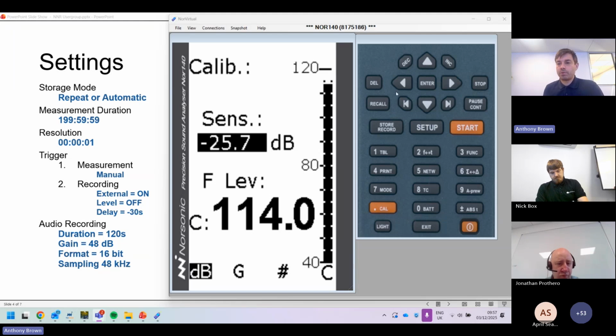So it's just trying to get to 114, which you do by pressing the dec or the inc key until you get to it. And if you keep pressing it, eventually it will go way past and you'll have to press the button to go the other way. So just get that as near as you can.